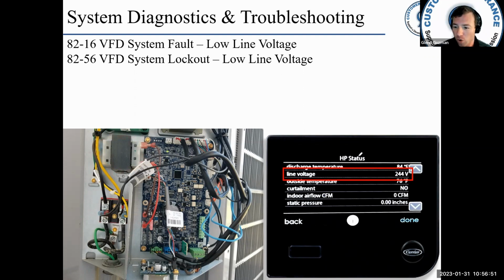Okay, now I can go onto the user interface, HP status, AC status, whatever, and look at my line voltage. It'll tell me right there. Okay, and it's reading that from the VFD directly. Now, if you have voltage that drops below 180 volts AC, then you get the code 8216. Okay. After 4 occurrences in 1 hour, then you get the 8256, which is a lockout for 2 hours.